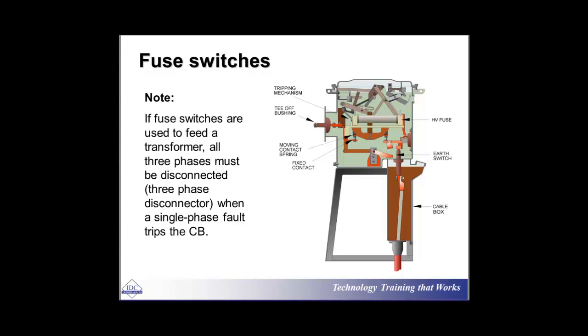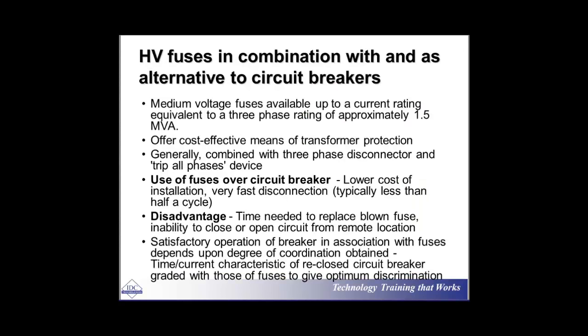If fuse switches are used to feed a transformer, all three phases must be disconnected when a single-phase fault trips the circuit. That's a must for all kinds of circuit breakers. You have a switching device on phase A, one on phase B, and one on phase C — a three-phase system. Even if you have a fault on phase B, it will not be acceptable if just phase B is disconnected while phases A and C are still working, because you will have excessive over-voltage on the other two phases and the system will automatically shut down.